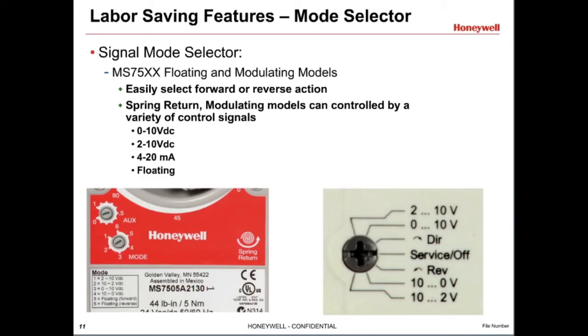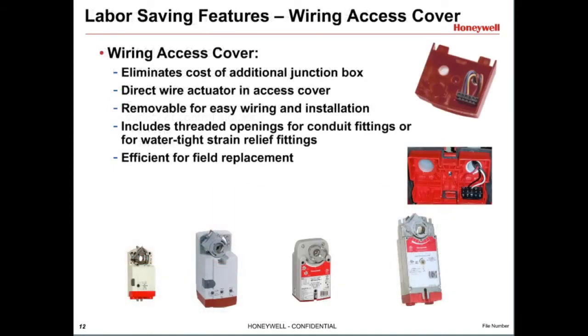Sylk communicating actuators need to be configured with an address to communicate properly with the controller. This is easily done the same way. Simply rotate the selector dial. All the recent Honeywell DCAs come with easy-to-access wire terminal covers. Simply remove the access cover screw and pull the cover away from the actuator. Now you can wire directly to the terminal blocks on the access cover. This makes wiring easier, especially in tight spaces, and can help eliminate the cost of an additional junction box. The access cover also has threaded openings for conduit fittings or watertight strain reliefs. It also makes field replacement quick and easy.